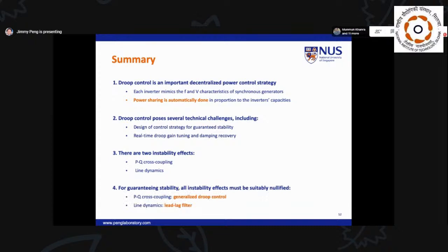To this end, a method to ensure stable power sharing under any Droop gains, any number of inverters, and any topology has been presented in this seminar. The proposed compensator is coupled with the generalized Droop to remove the cross-coupling and line dynamic effects. The compensator design also enables the operator to change the connectivity and operating mode of the individual inverters at will, without the need to run a full system stability analysis. This realizes the concept of plug-and-play inverters within a microgrid.